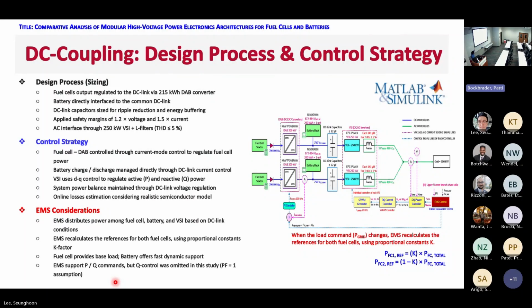Regarding the EMS, it distributes the power among the fuel cell and battery VSI based on DC conditions. It continuously recalculates power references using proportional constants such as the K factor to maintain consistency with AC coupling. The study assumes unit power factor, so reactive power control is not included. This architecture allows power management to be consolidated at the DC stage, improving efficiency and enabling high power operation.